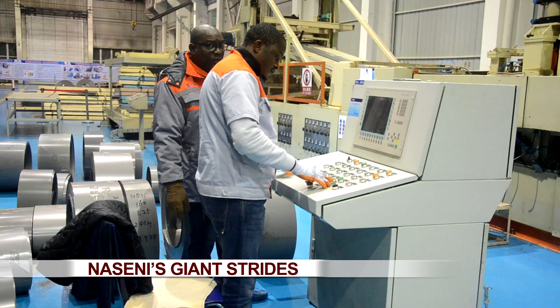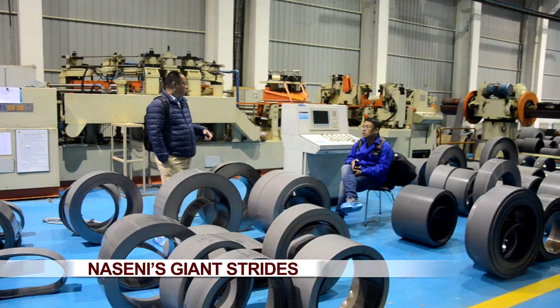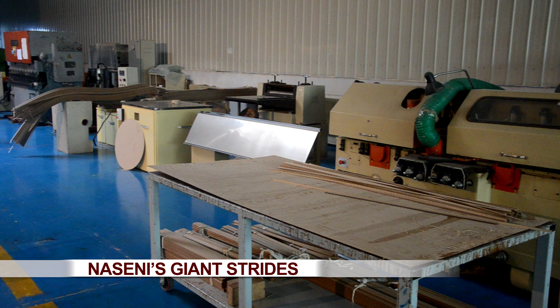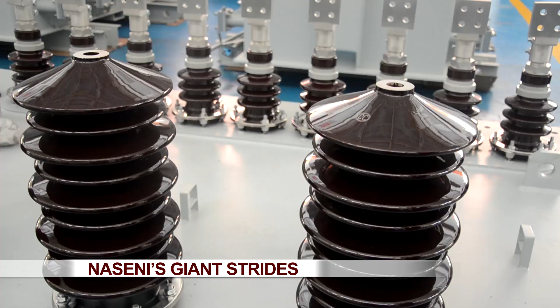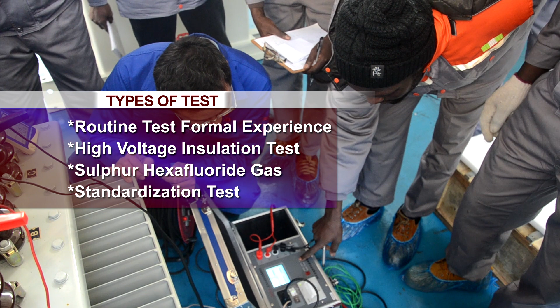The High Voltage Testing Laboratory is aimed at developing indigenous capacity in high voltage testing. This is a compulsory component of the technology acquisition and domestication of power equipment technology, as well as successful power supply and industry. The test center, designed for testing the capacity of 6,300 kVA and 132 kV voltage level transformers, can perform a series of tests including routine test, formal experiment, high voltage insulation test, and sulfur hexafluoride gas standardization test.